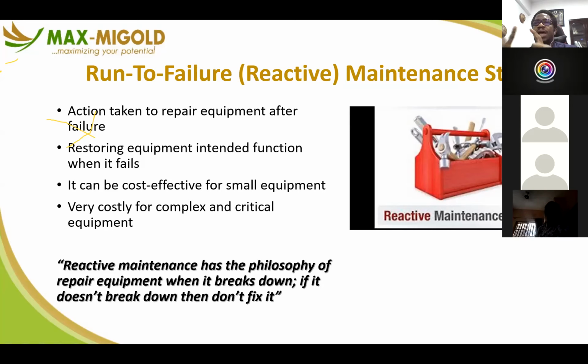I see some critical assets that are core to the mission of the organization that can be run with run to failure, for example, because you have redundancies. You have a massive server that serves the organization. There's concern about the FM team coming into that server room because they could mess with things and push cables around that will lead to all kinds of issues, right? And because of that, management has decided to provide 3 equal capacity air conditioning systems for that server room, whereas only 1 is what runs the server room.